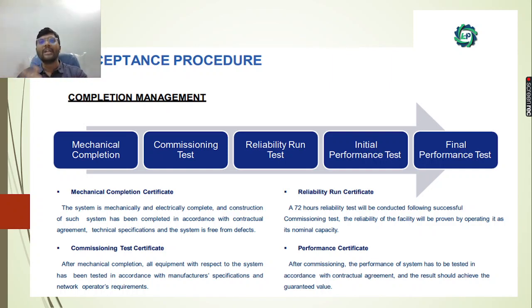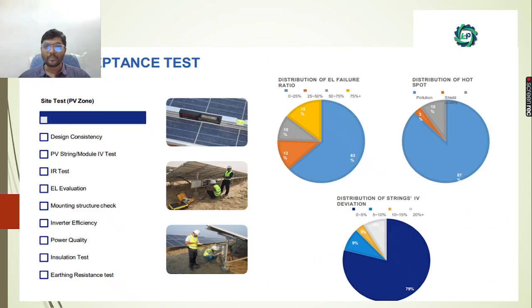Next is the reliability run certificate. That is very much important. You need to run the entire system for 72 hours, approximately 3 days, and run it successfully. Only then can we provide this reliability run certificate. Then the most important thing is the performance certificate. After commissioning, the performance of the system has to be tested in accordance with the contractual agreements. Based on the result, we should achieve the guaranteed value.